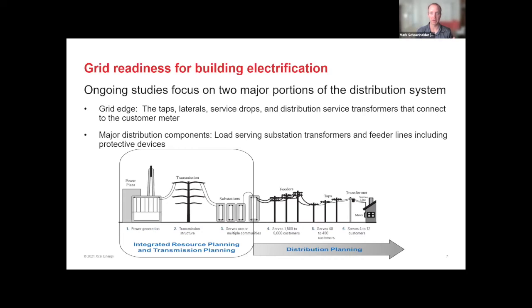So we build out infrastructure so that we're able to serve customers at 25 below 0. There aren't air source heat pumps that have a meaningfully better coefficient of performance than 1 down at that temperature. So effectively, you're at electric resistance down there. And now the electric load for that customer, the peak load, which they may use 2 hours every 5 or 10 years, is very high. But they still need to have an electric service. Their panel needs to be able to meet that unless they have a different backup source.